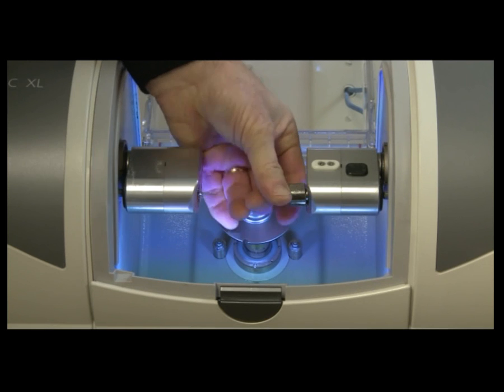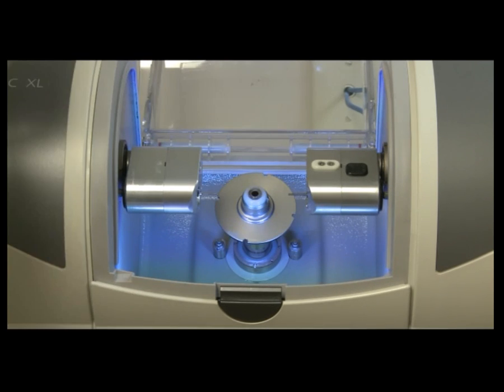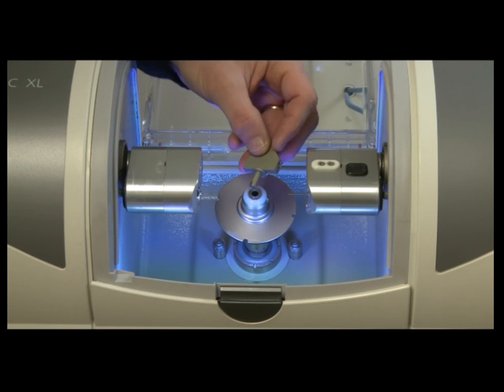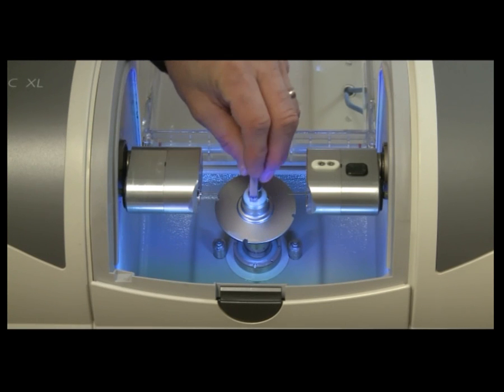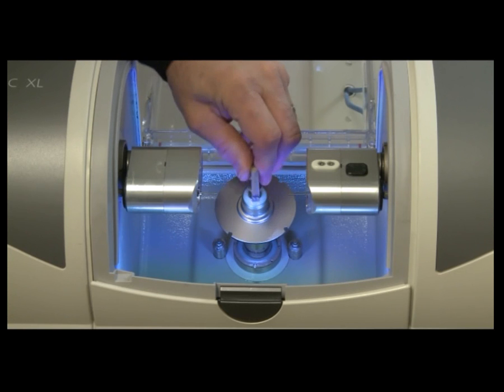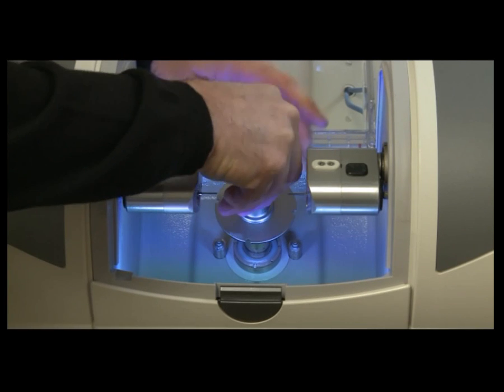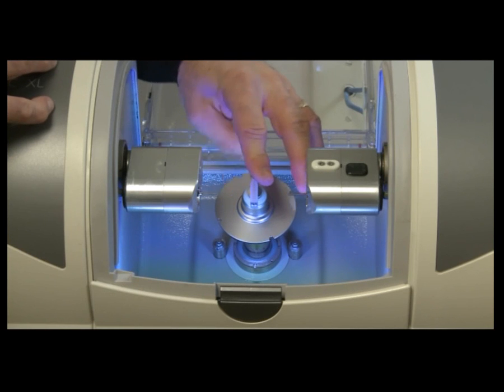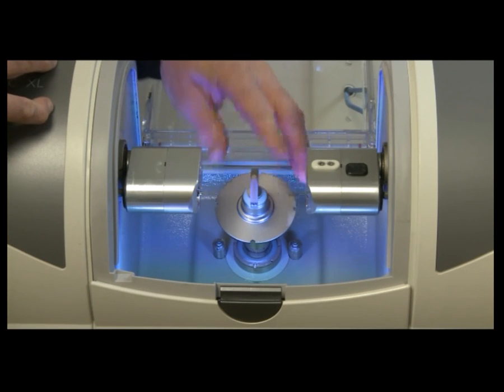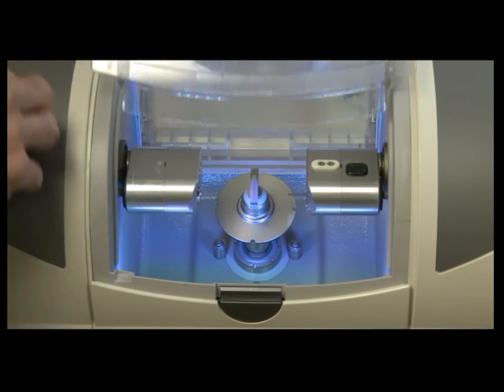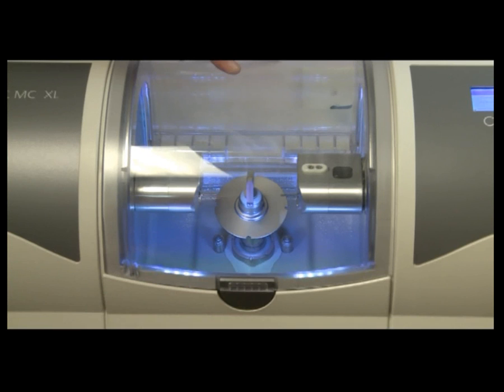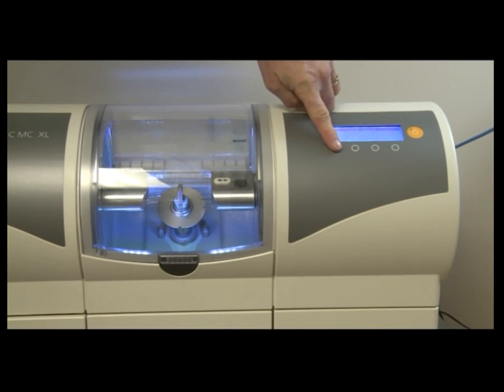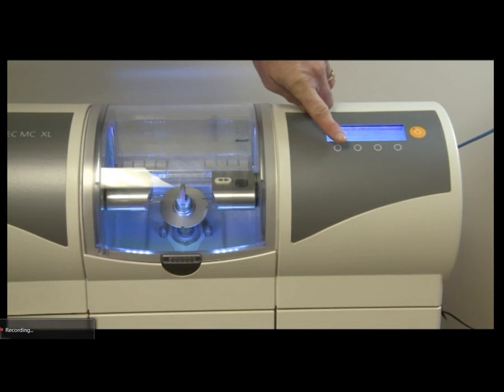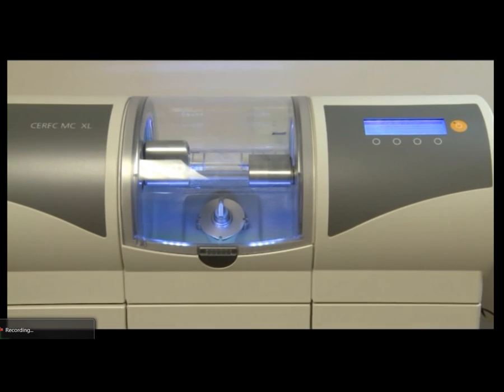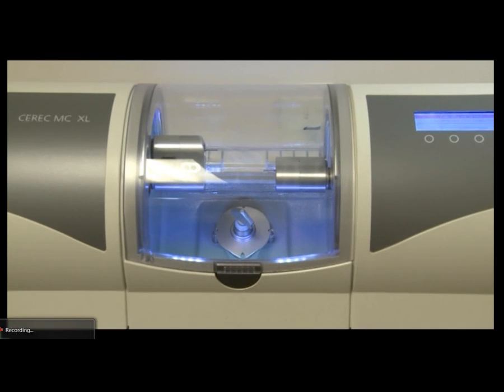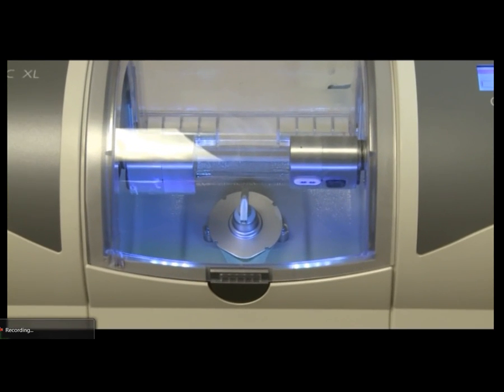Then, when you go to put in your specimen, like is going to happen right here, that center section will be out, and you're going to drop the whole section that's much longer than that into place. Move it until you see it's locked, and once it's locked, you're going to tighten it again with your hex wrench, with your Torx wrench actually. Once it's tightened, just close the door. Once your door is closed and latched, then you go to the top right, push the start button, and then it will continue to do the calibration. Again, it will take anywhere from 3 to 5 minutes, and I would suggest that Patterson does this once a year, and you can do it once a year.